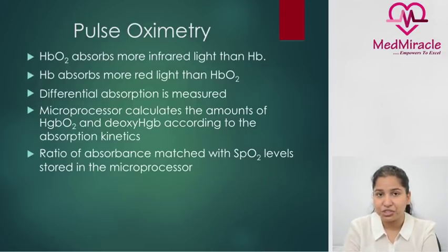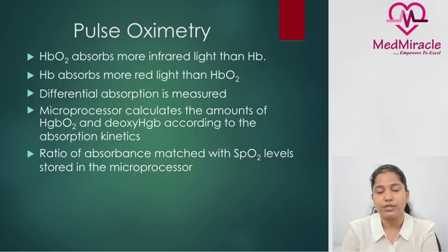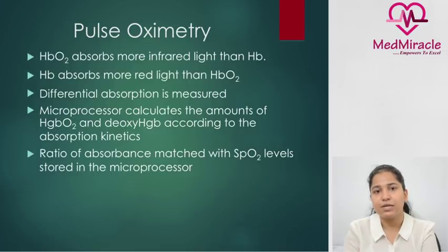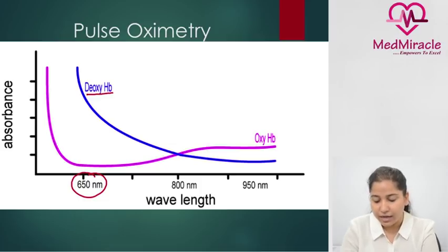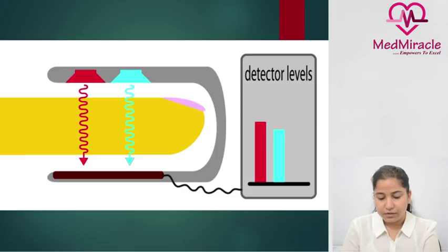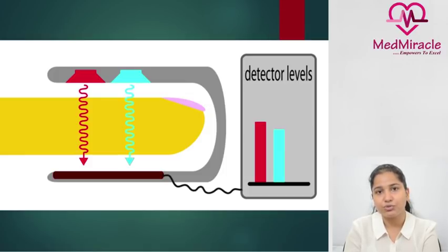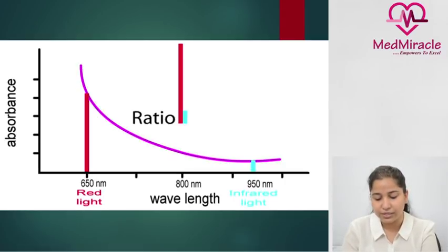Differential absorption is measured by the pulse oximeter, and a microprocessor calculates the amount of oxyhemoglobin and deoxyhemoglobin according to the absorption kinetics. A ratio is created and accordingly a value known as SpO2 — saturation of oxygen — is displayed. At 650 nanometers, deoxyhemoglobin has higher absorbance, and at 950 nanometers, oxyhemoglobin has higher absorbance. The ratio of these two absorptions is calculated to determine the SpO2 value; higher the ratio, higher the saturation in blood.